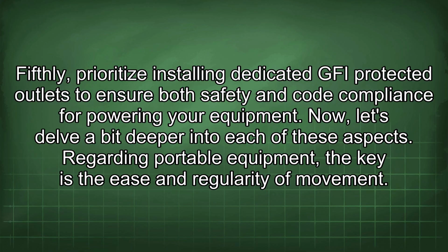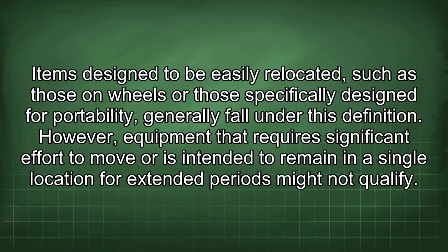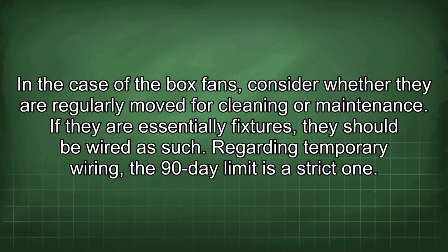Regarding portable equipment, the key is the ease and regularity of movement. Items designed to be easily relocated, such as those on wheels or those specifically designed for portability, generally fall under this definition. However, equipment that requires significant effort to move or is intended to remain in a single location for extended periods might not qualify. In the case of the box fans, consider whether they are regularly moved for cleaning or maintenance. If they are essentially fixtures, they should be wired as such.